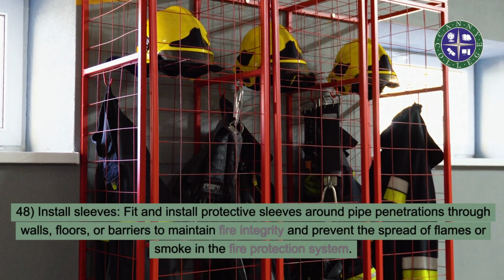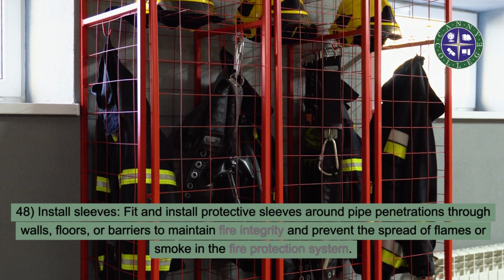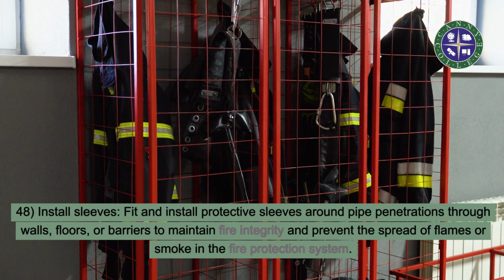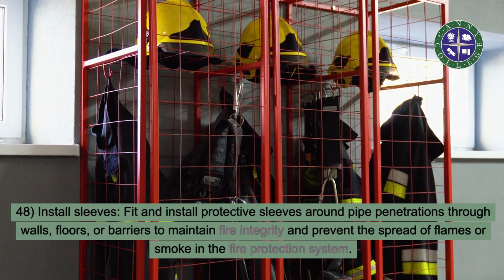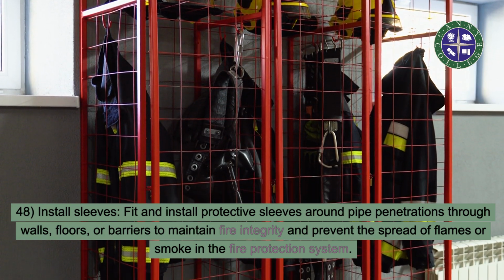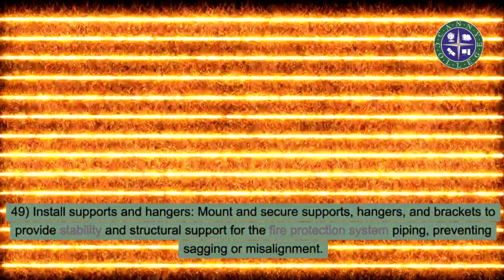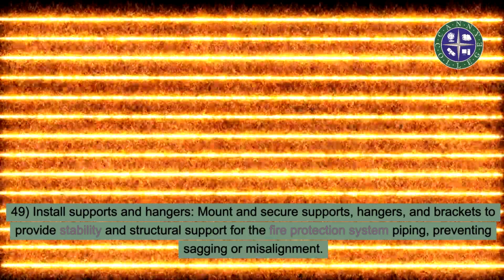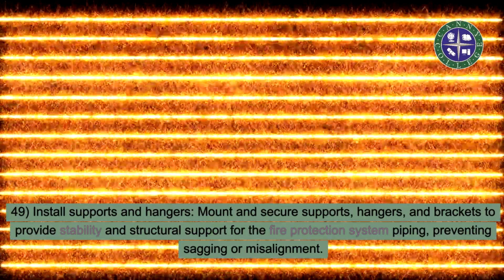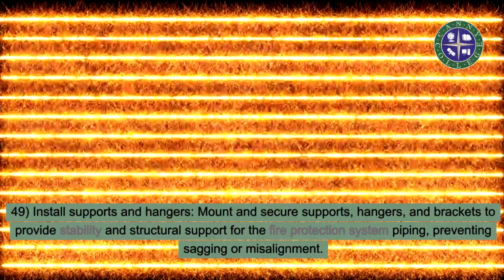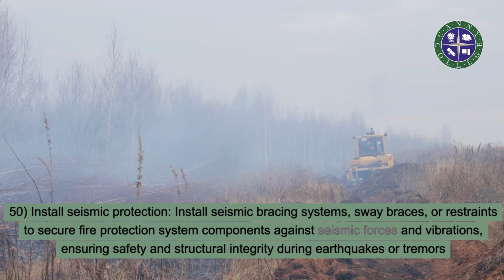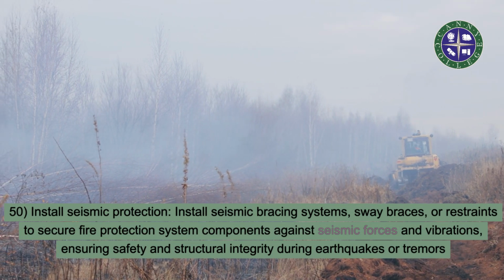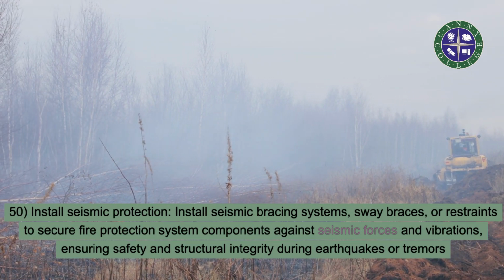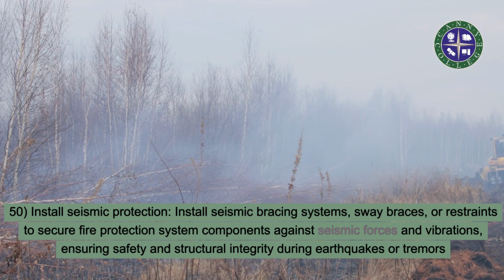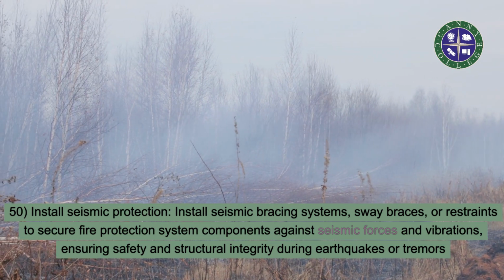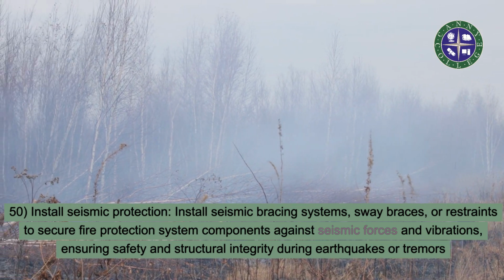48. Install sleeves. Fit and install protective sleeves around pipe penetrations through walls, floors, or barriers to maintain fire integrity and prevent the spread of flames or smoke in the fire protection system. 49. Install supports and hangers. Mount and secure supports, hangers, and brackets to provide stability and structural support for the fire protection system piping, preventing sagging or misalignment. 50. Install seismic protection. Install seismic bracing systems, sway braces, or restraints to secure fire protection system components against seismic forces and vibrations, ensuring safety and structural integrity during earthquakes or tremors.